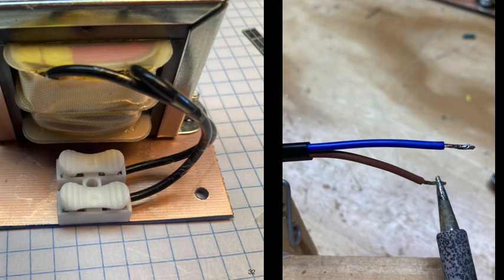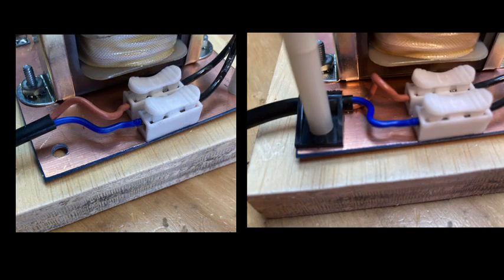Back to the line voltage side. Insert both transformer wires in one side of the spring-loaded connector. Now make sure they're firmly inserted. You should not be able to easily pull them out. Next, split the line cord back about 2 inches and strip off about 3/8 of an inch of insulation and tin the wire. Insert the line cord ends into the connector. When you install the plexiglass cover hardware, you'll install the strain relief over the line cord. Do not forget this step.